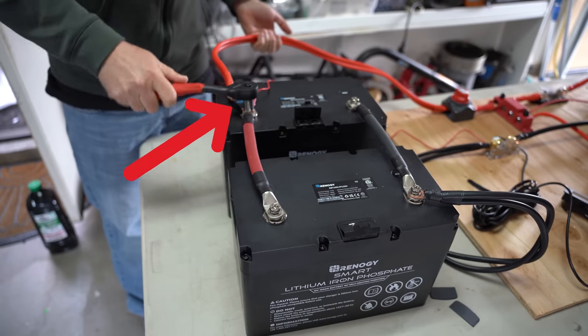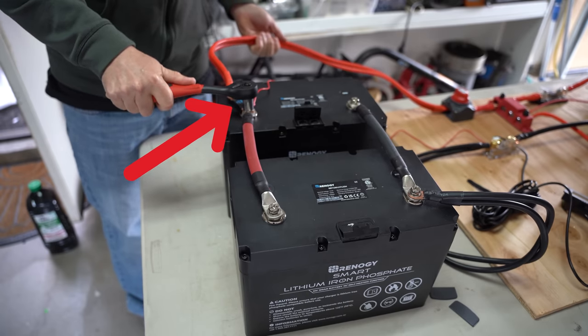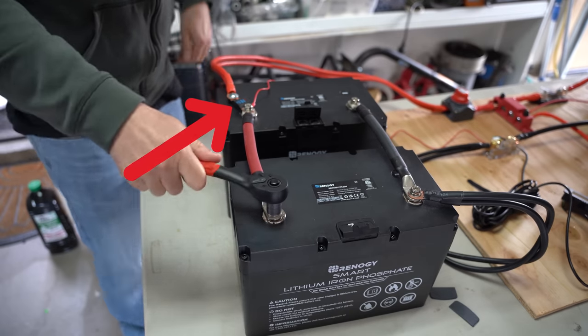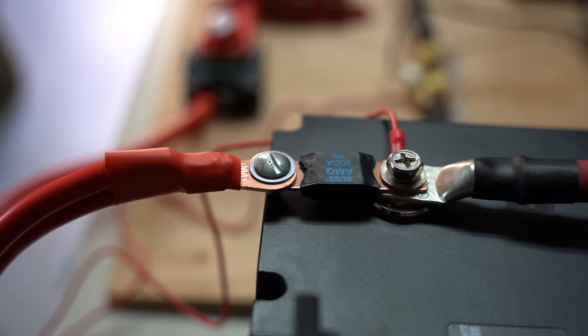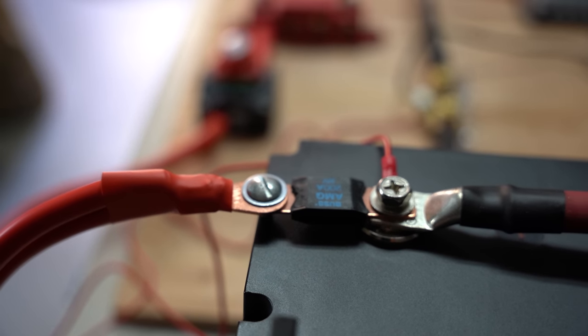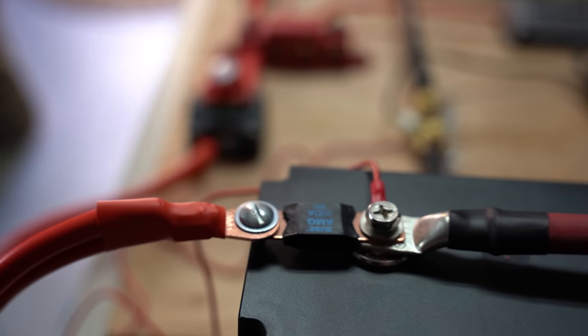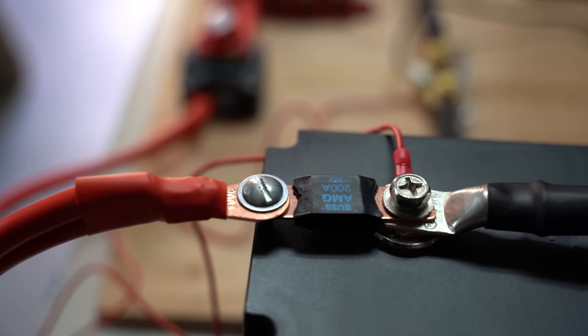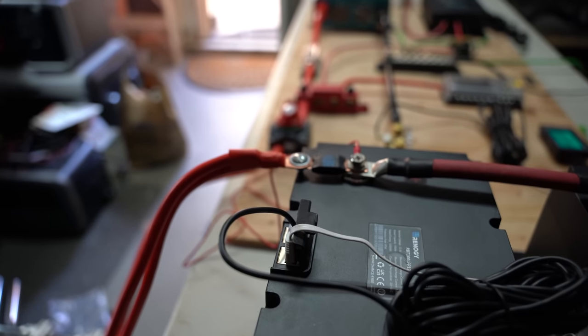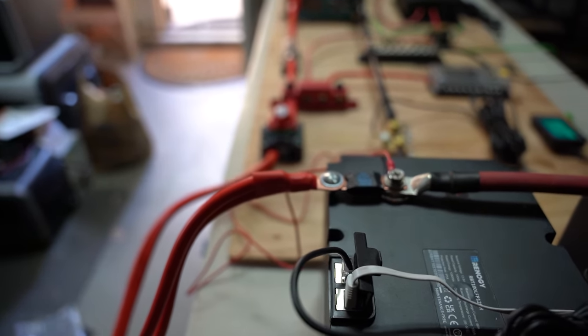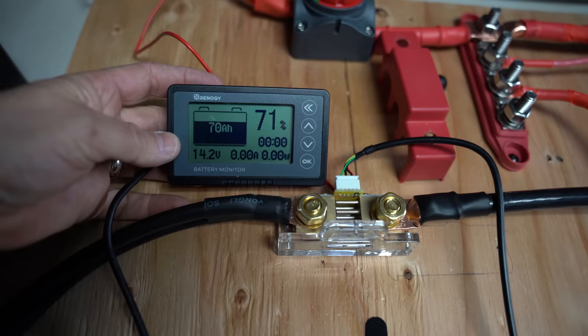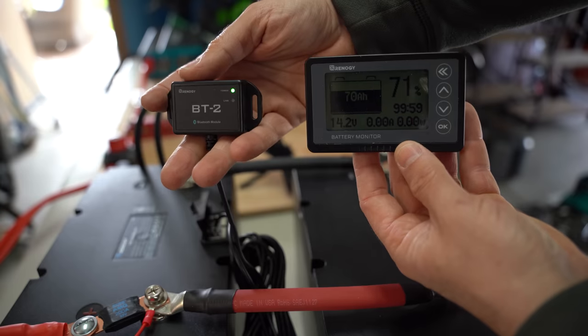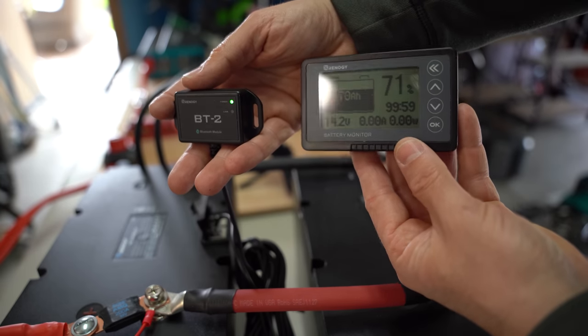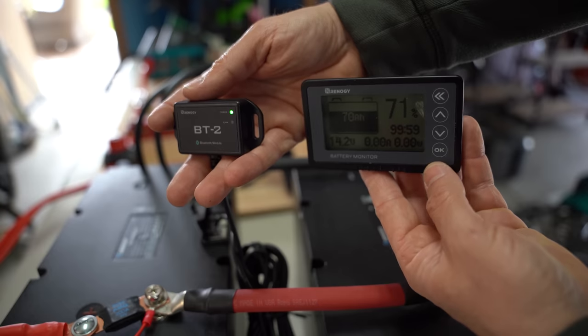Also note that I've placed a 200 amp fuse on the positive terminal that our cable going to the system is connected to. Since our system is a 200 amp setup, that's the max current that we can ever pull from these batteries, and our wires are rated to only handle 200 amps. So it's important that we put our fuse right here at the point of origin for our power to protect all of the cables. Earlier we mentioned installing a shunt. As you can see here, the shunt is connected to our battery via this small cord, and we can then see the status of the battery.